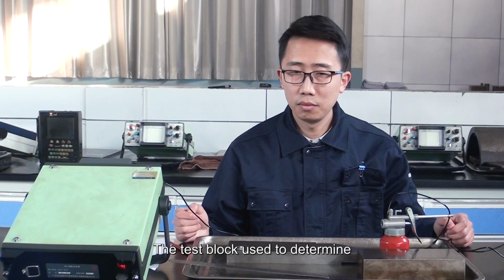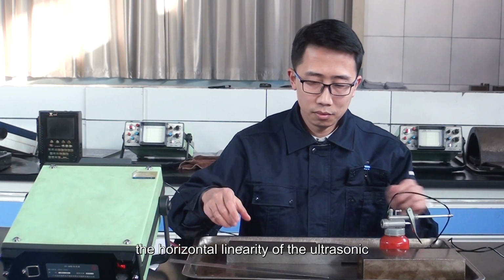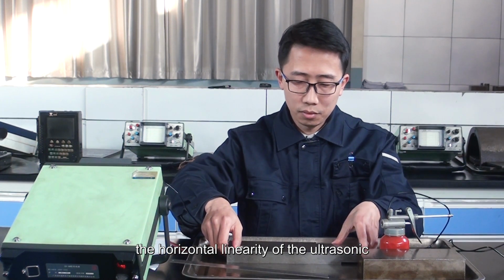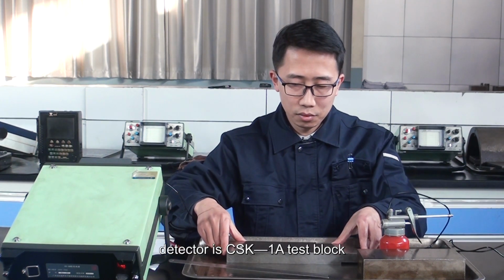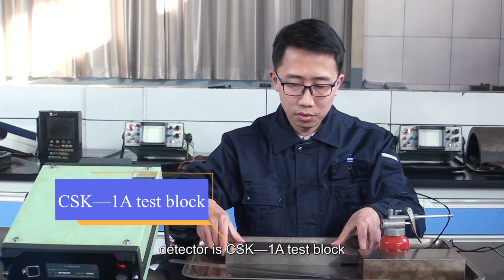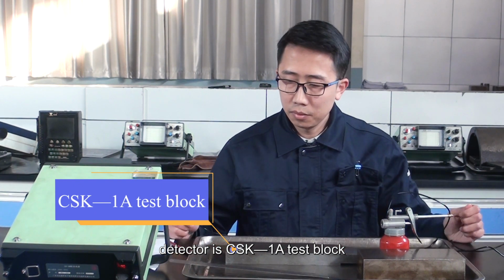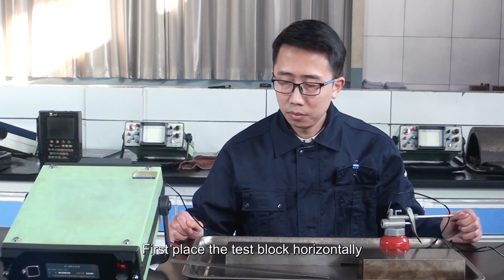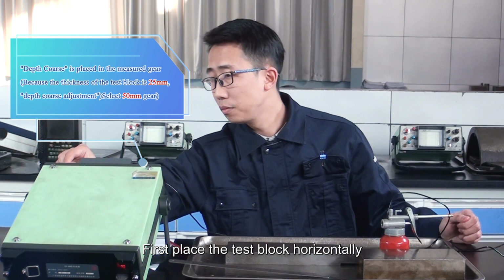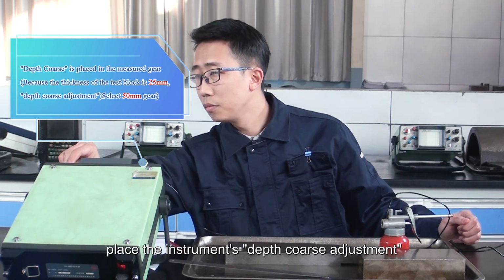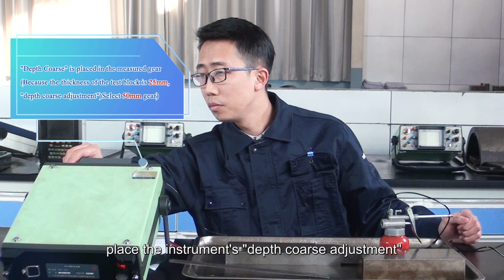The test block used to determine the horizontal linearity of the ultrasonic detector is the CSK-1A test block. First, place the test block horizontally. Place the instrument's depth coarse adjustment at the gear to be measured.